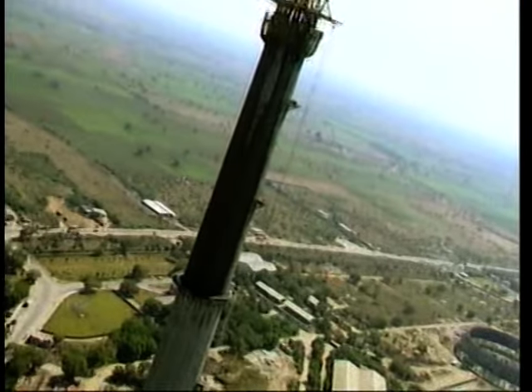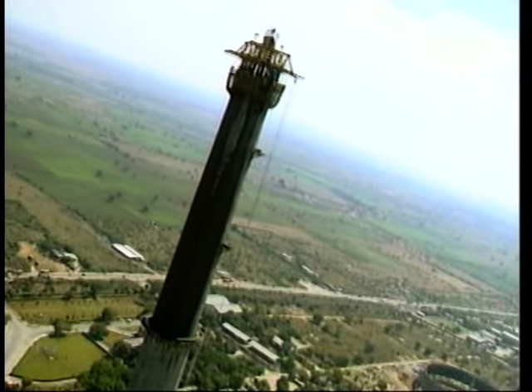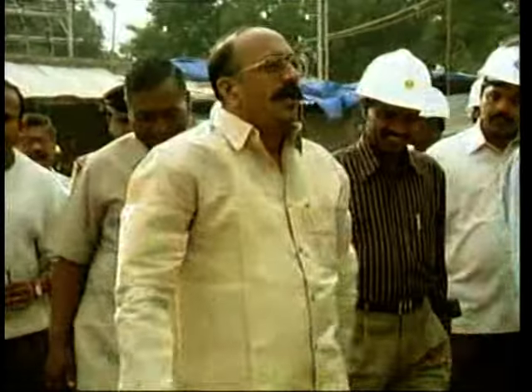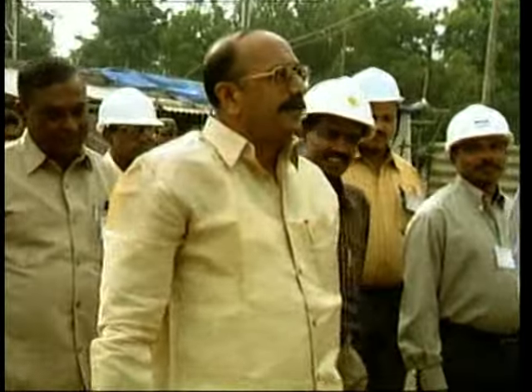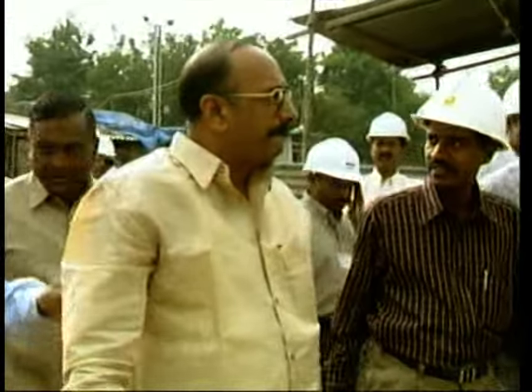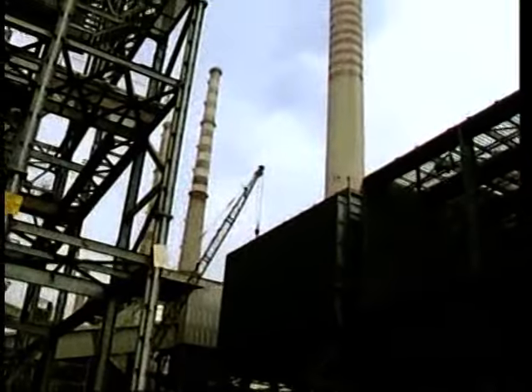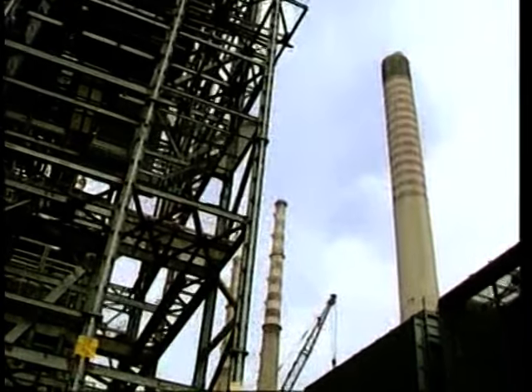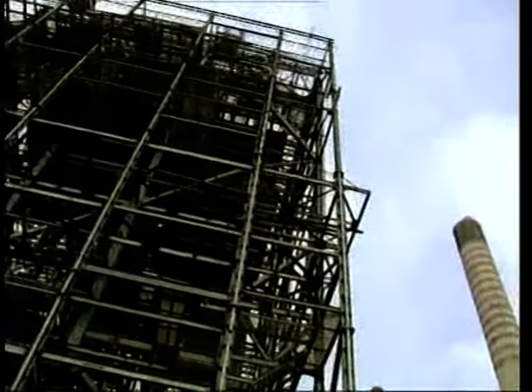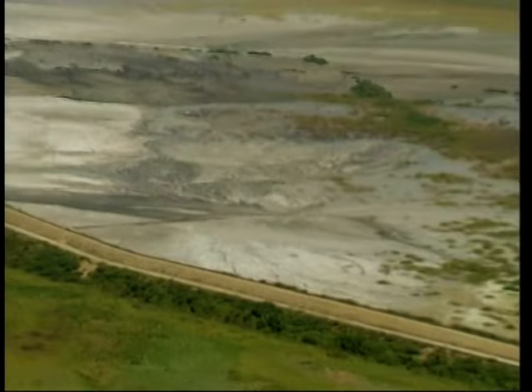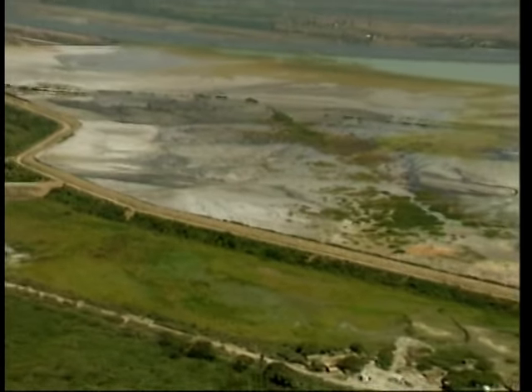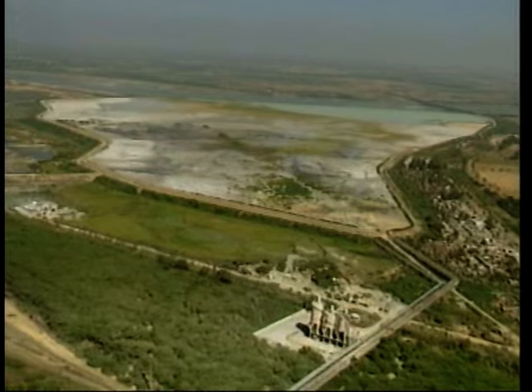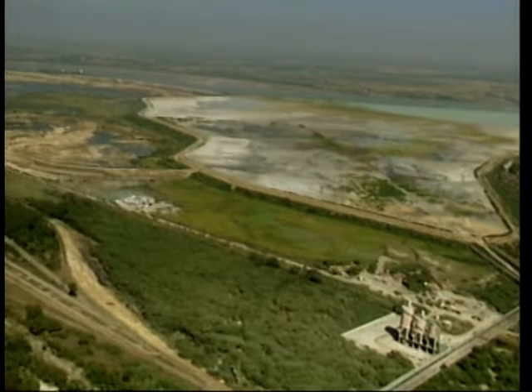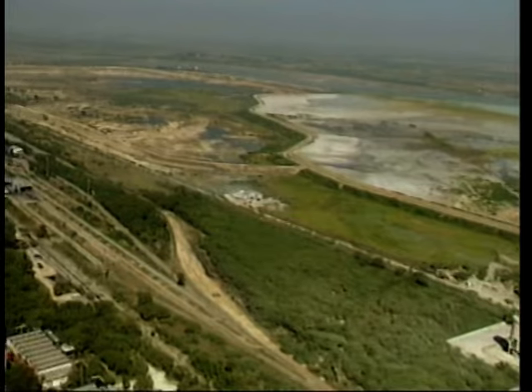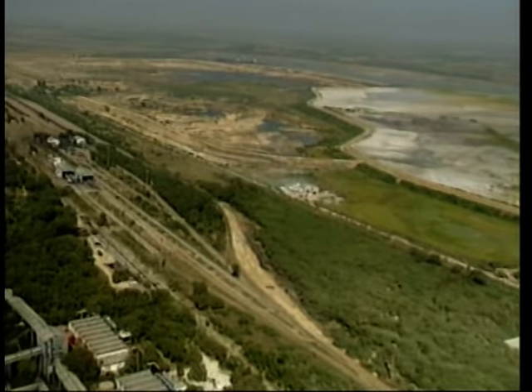The last bucket of cement to be used for the construction of chimney number 7 was placed by the Minister for Energy for the state of Karnataka, Shri Veer Kumar A. Patil, in the month of December 2001. Construction of the chimney is considered one of the milestones in the construction of the power station. And then this ash is mixed with hot water and will be pumped to an ash pond. RTPS has two ash ponds. One was constructed in the year 1983, which is almost filled up now. After it fills up, the ash will be dumped in the second ash pond.